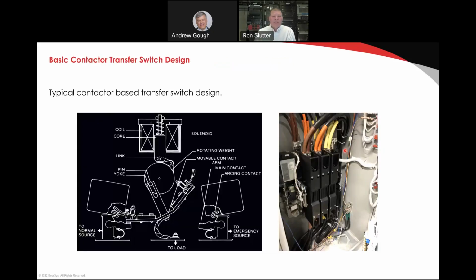Here is a representation of the internal workings of an ATS. So the ATS on the left-hand side, the picture here, represents a contactor-based typical ATS design. Why contactor-based? Because contactor-based designs for ATS last hundreds of thousands of cycles. So these contacts, as you can see that are shown here, are able to withstand a lot more transfers than if we were to use the circuit breaker-based design, which I'll show you in a minute. So this is an old ASCO example, but it does show you very easily how the transfer switch works. You can see here on the left side, we have the normal connection. On the right side, we have the emergency connection, and on the bottom, we would connect to the load.